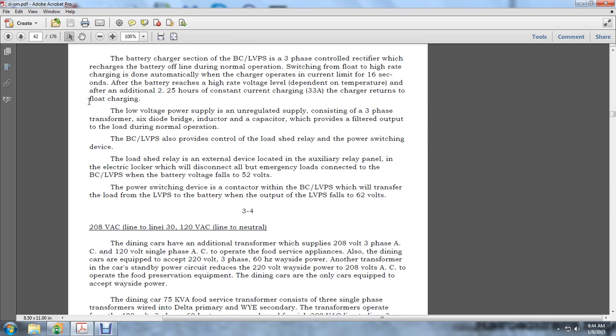208 volts line to line, 3-phase, and 120 volts line to neutral. The dining cars have additional transformers, which supply the 208 volt three-phase AC and 120 volt single phase AC to operate the food service applications or appliances. Also, the dining cars are equipped to accept 220 volt three-phase 60 Hz wayside power. Another transformer in the car standby power circuit reduces the 220 volt wayside power to 208 volts AC to operate the food preservation equipment. This dining car is the only car equipped to accept wayside power.